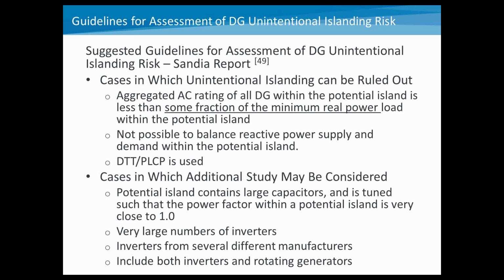In general, what it said was unintentional islanding can be ruled out in these types of scenarios. One, where the aggregated AC rating of all the DG is less than some fraction of the minimum real power within the potential island, and it's not possible if you can't balance the reactive power supply and demand within the island. So again, this is looking at the probability and possibilities of having matched power, both real and reactive, inside the island. And the other condition is if direct transfer trip or permissive power line carrier is used, you can pretty much rule out that unintentional islanding would occur.